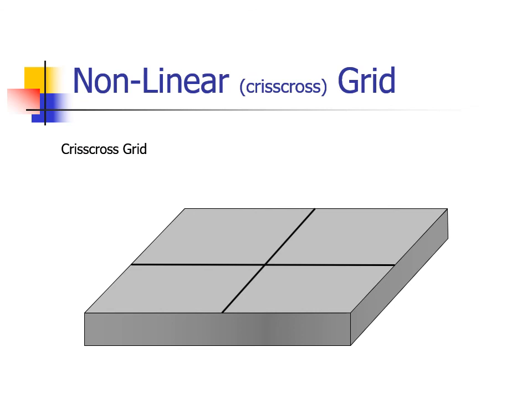Criss-cross grids have the advantage of superior ability to remove scatter when compared to their linear counterparts. A disadvantage is that you can't do any views that require a tube angle because you'll always be angling across one of the two grids.